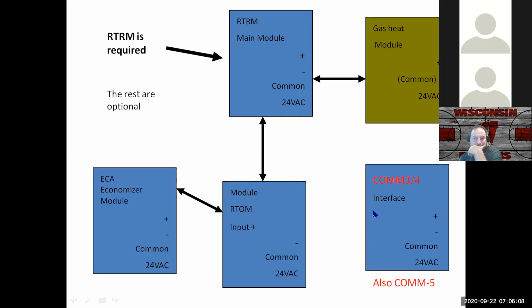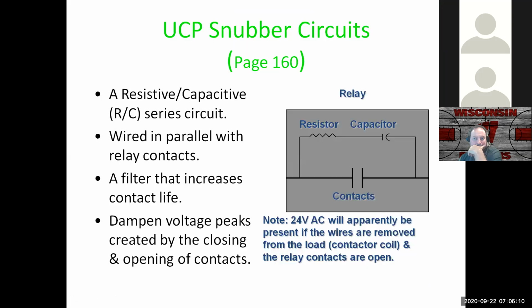Okay, so with that being said, there are some quirks with the systems that you need to be aware of if you're working on them. We've got some snubber circuits built into our controls, and basically what this does is it puts a resistor and a capacitor in parallel with the contacts to reduce inrush current. That prolongs the contact life on the board, but it also can throw some signals out to the system that can send you in the wrong direction if you're not aware of them.